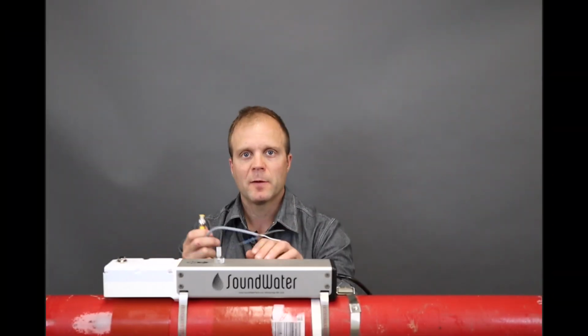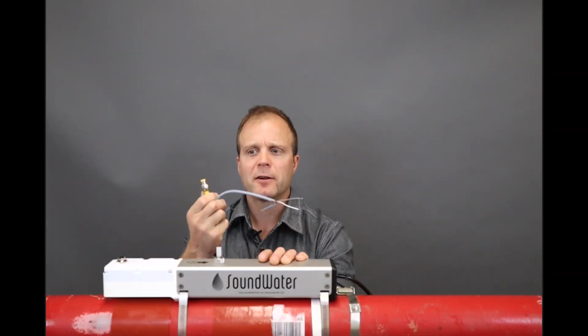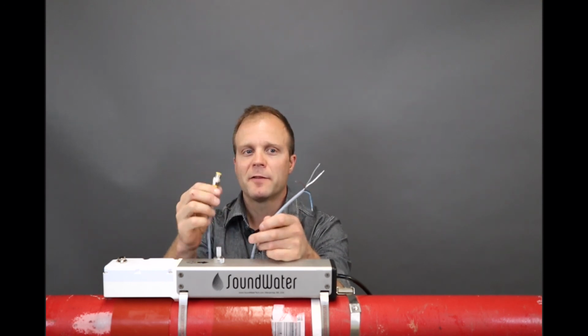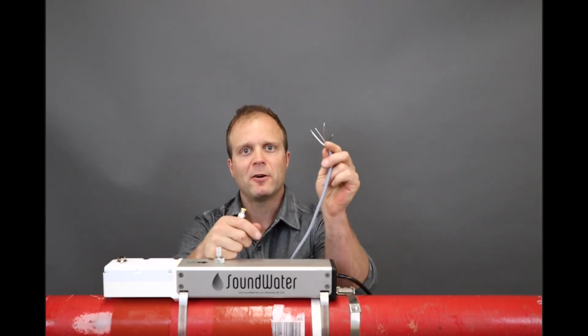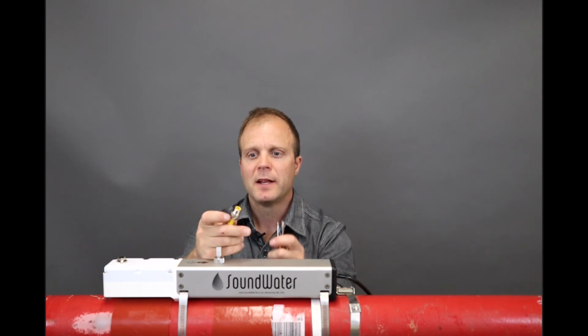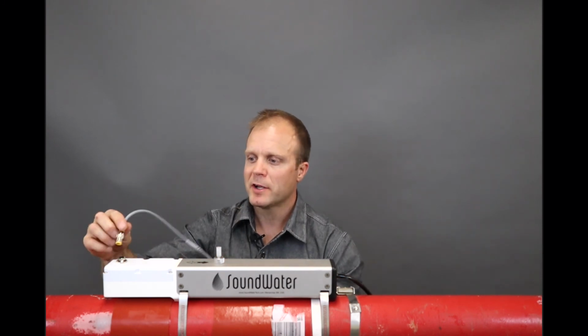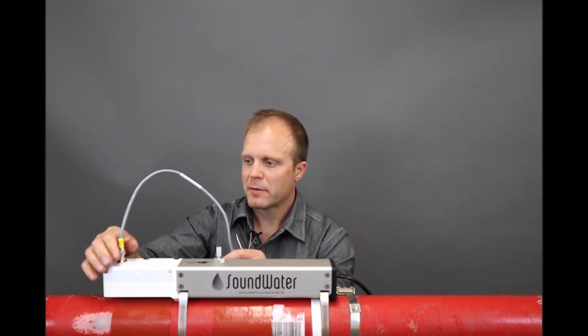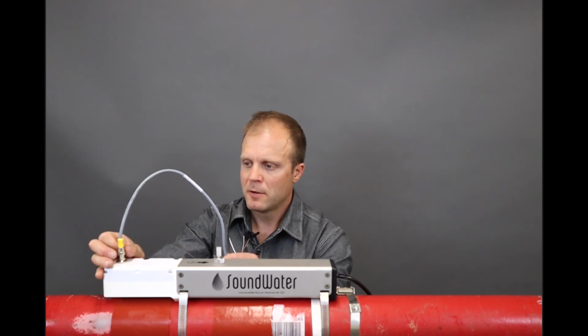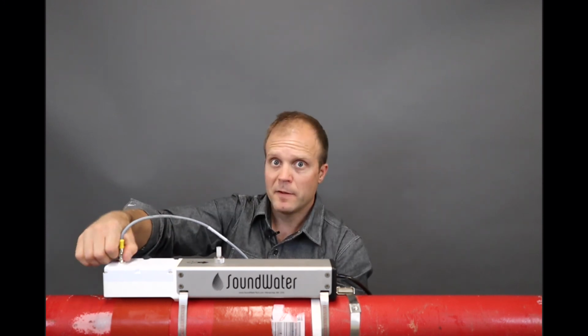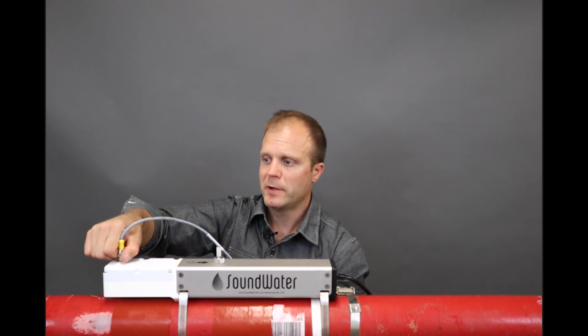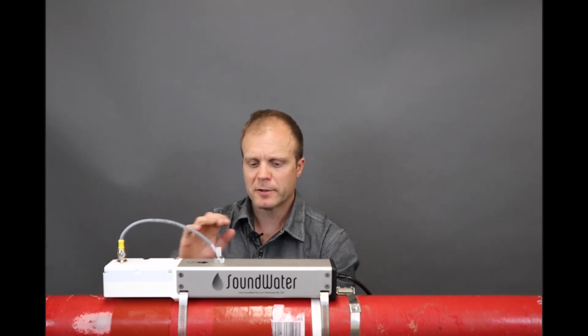So we're going to attach power now. The unit comes with this cable. It's a standard M12 connector. The cord set has a pigtail on the other end with 5 conductors. The meter has a plug here. We're just going to thread in the wire. And this has an O-ring seal on it, so you can leave this outside for years.